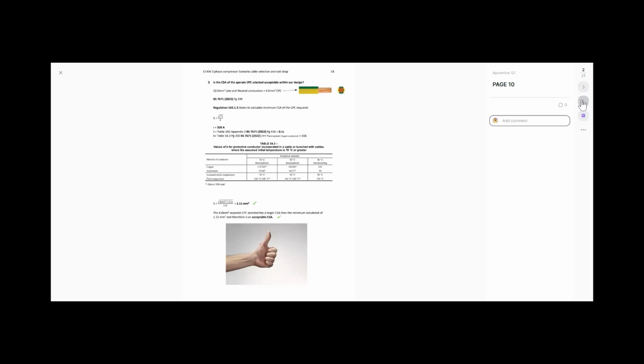So square root of 404 squared times 0.1 divided by 143 equals. So I've got a minimum cross-sectional area that we're going to need of 0.89 millimeters squared. Based on that amount of fault current, that amount of time the device is going to take to disconnect, and the K value based on the protective conductor that's not running in the same cable, it's not incorporated with it, it's run separately. So K value is 143. So the minimum size that we need to run with that SWA is 0.89 millimeters squared.